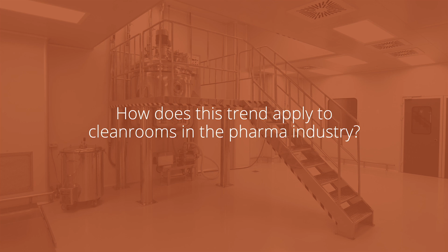How does this trend apply to clean rooms in the pharma industry? So various types of clean rooms. And when we say types of clean rooms, we talk about industries from pharma to microelectronics to aerospace. And in pharma, in the EU standard and the FDA standard, they actually allow for a performance-based solution that defines air velocity and particle count, not specifically air change rates. Most of the industry assumes that air change rates define the other two, but the reality is now that there are better and more reliable particle counters, you're able to increase your performance in the EU and FDA standard. It takes a little bit more design time and a little more operational calibration of particle counters, but it's a very nice way to save energy and get more efficient in those markets.